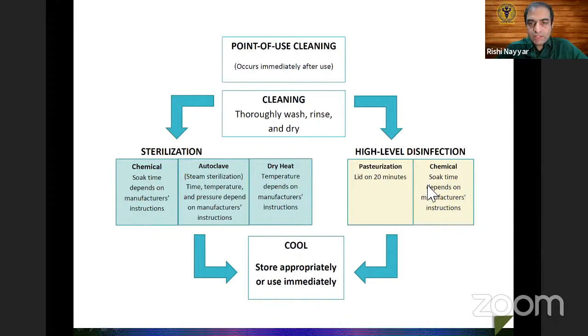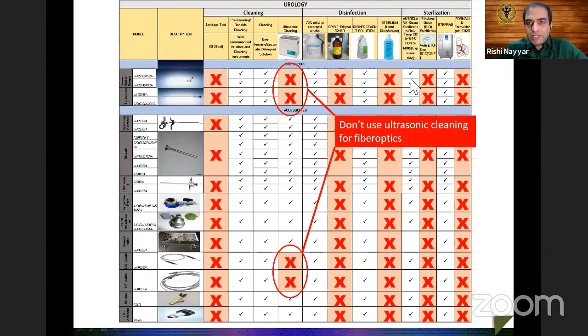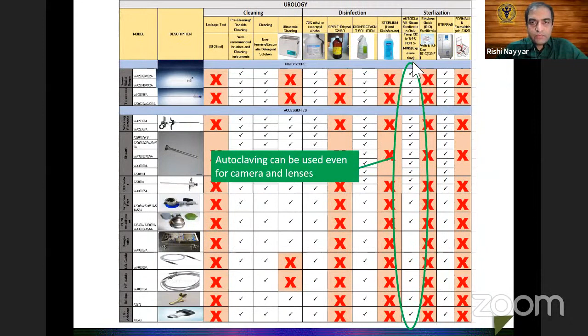So this is my last slide. I would just give you a brief overview that ultrasonic cleaning should not be used for instruments which have fiber optics involved in them, because they create cavitation bubbles which can injure the fibers, and therefore the fiber optics can be damaged. Formaldehyde should not be used because it is toxic, and most of the time it does not provide sufficient sterilization for the time it is used. Autoclaving can actually be used even for lenses and the camera, and wherever feasible this should be used.